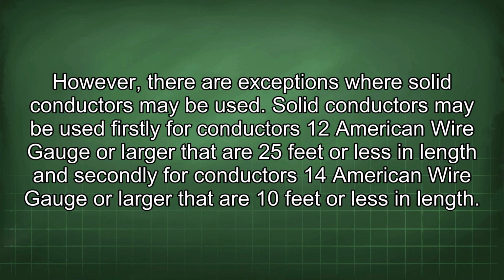Solid conductors may be used firstly for conductors 12 American wire gauge or larger that are 25 feet or less in length, and secondly for conductors 14 American wire gauge or larger that are 10 feet or less in length.